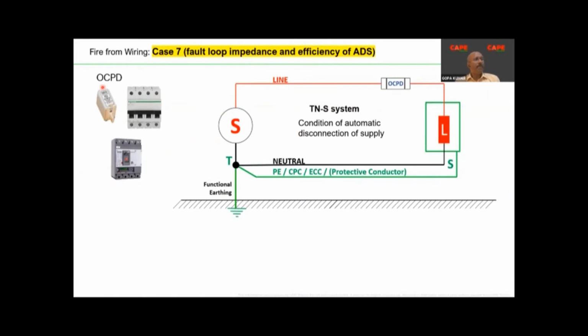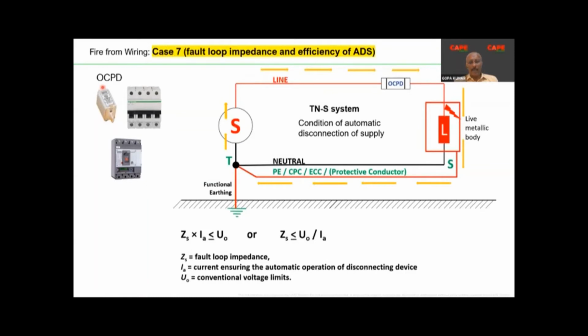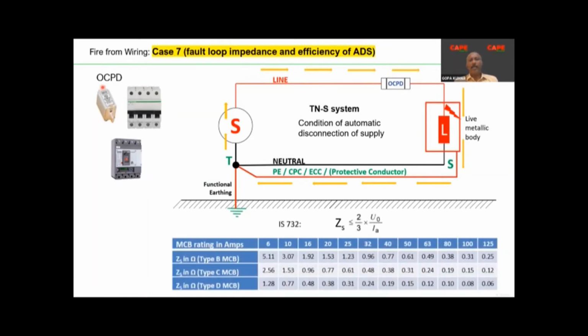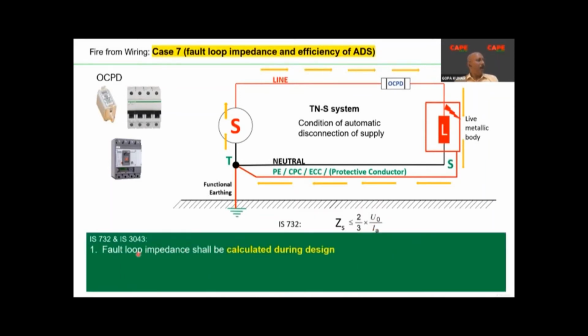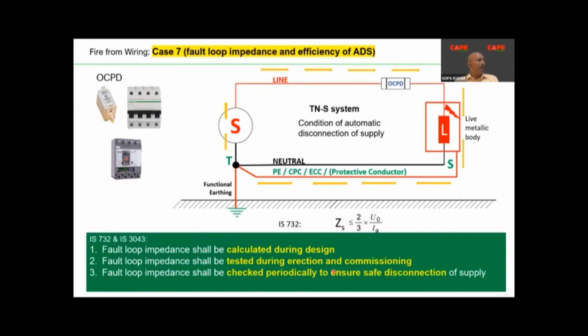Then the seventh point, fault loop impedance. Fault loop impedance means the impedance of the circuit, which is a very critical subject that needs to be taken care of during design. The calculations are very well explained in the standard. A lot of improvements have happened in IS 732, with a very good calculation and the methods of calculation also included. Fault loop impedance shall be calculated during design, tested during erection and commissioning, and periodically tested to ensure safe disconnection, especially if you have loose contacts in your wiring. This test will show you that the device is not tripping, you are in danger.